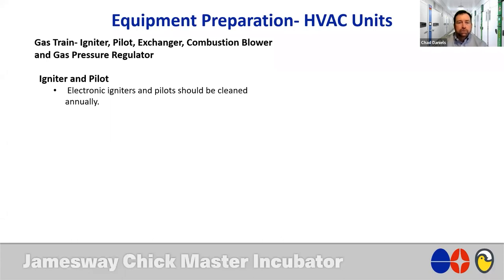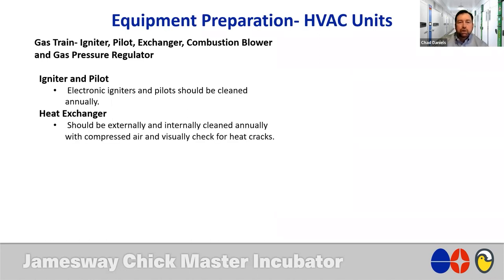In most pilot systems, you've got a sensor there that proves the pilot is on. And if that sensor is not cleaned, then the ignition of the combustion blower or the combustion won't be allowed to complete its cycle. So it's important that that get cleaned. The heat exchanger itself should be externally and internally cleaned, generally just with compressed air. And you want to make a visual check of that to make sure you don't have any heat cracks.